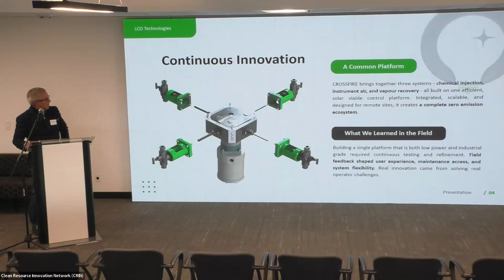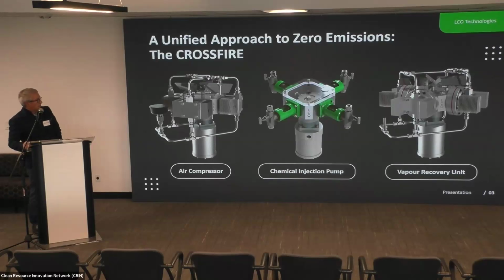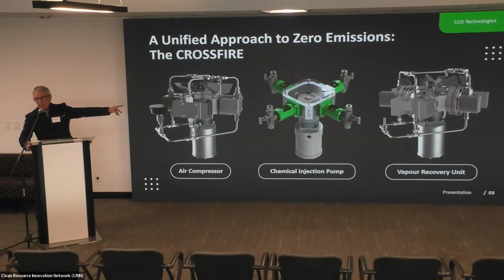Really, feedback from the field was largely responsible for the changes we made. Let me back this up a bit. The air compressor has been a real challenge in the field. On the chemical injection pump, we're on about the 5th or 6th revision, but on the instrument air compressor, we're on like the 45th revision. It has been difficult from the get-go to use solar power to compress air.